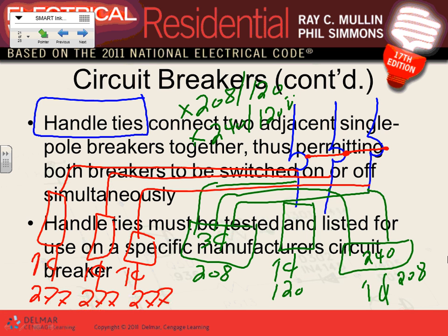There's restriction. If they are molded circuit breaker, one big circuit breaker, then you can feed any voltage up to 600 volts for the most part. The handle must be tied, so it means you can't take a string from your wife's sewing machine and tie them together or custom design the tie between them, right? When you gang them, the handles have to have a groove that goes right through them to gang these. Everybody knows when we say ganging, there's 1, 2, 3.